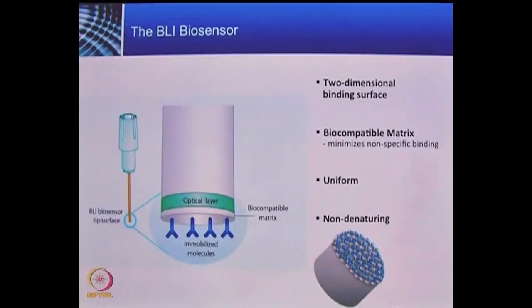The core part of the BLI technology lies with the biosensor. If we take a close look at the biosensor, it is actually made of optical fiber at the end. At the very end of the biosensor is a two-dimensional biocompatible matrix. This matrix allows you to immobilize molecules on the surface to allow further analysis of biomolecule interactions. The benefit of using this patented biocompatible matrix is that it is very uniform, it minimizes non-specific molecule binding to the membrane, and it is also non-denaturing.